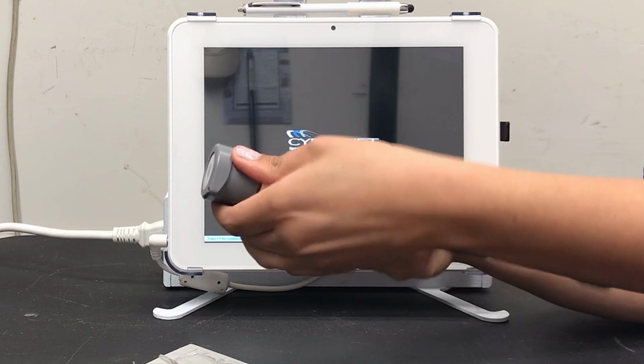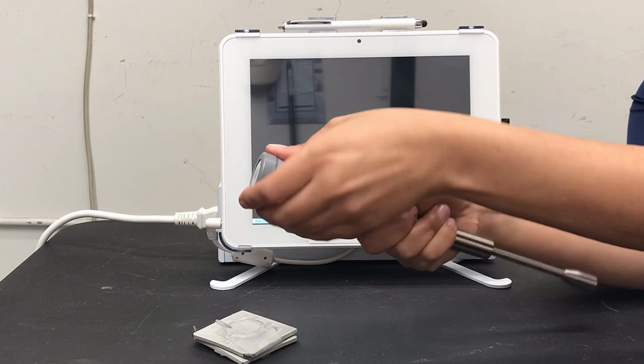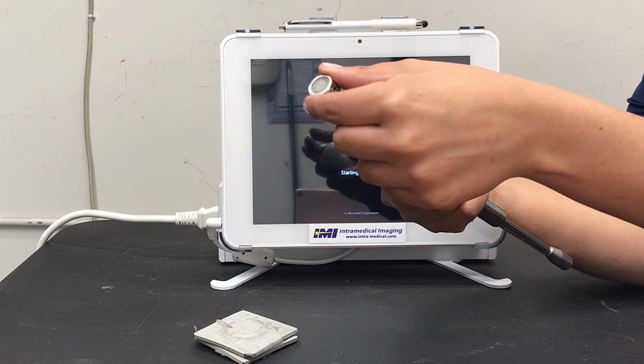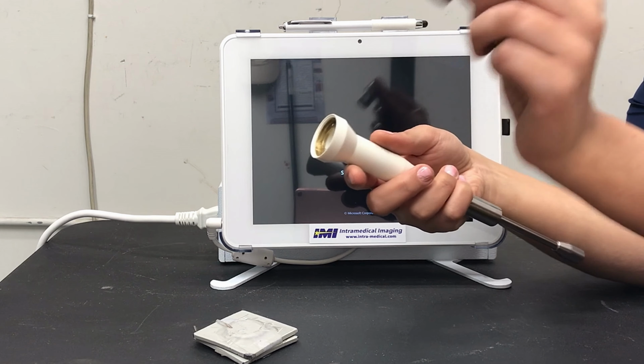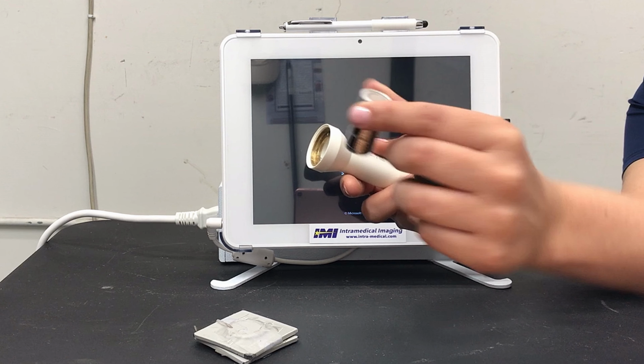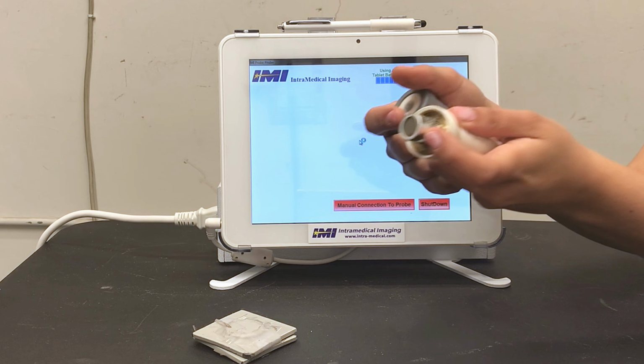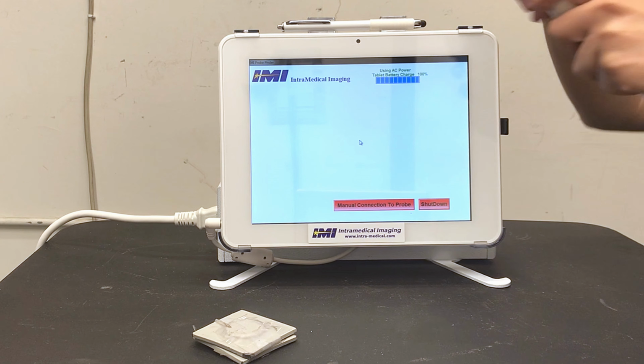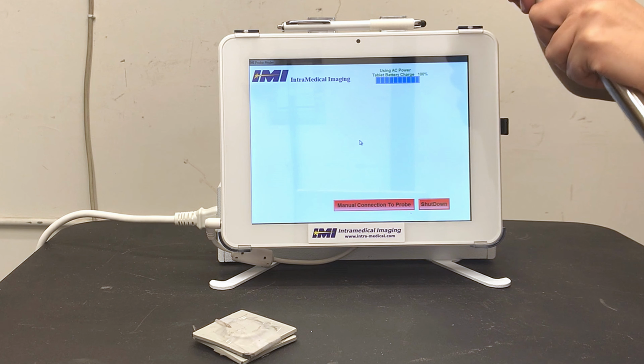To change the probe's battery, twist off the gray housing cap. The negative side of the lithium-ion 123 should pop out. If you're sterilizing your probe, be sure to have a fresh battery in the probe before it undergoes sterilization through hydrogen peroxide and not autoclave methods.